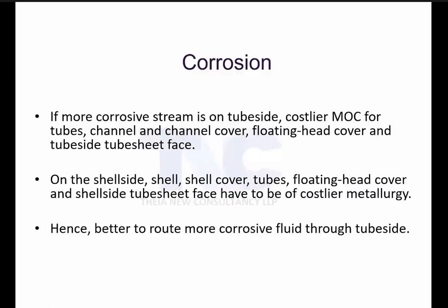So remember, when you see a highly corrosive fluid, it is recommended to always put it in the tube side. Otherwise, if you put the corrosive fluid in the shell side, the shell has to have a costlier MOC, and the tube also has to have a costlier MOC. Clear? So remember, this is always good. You don't need to do much discussion.